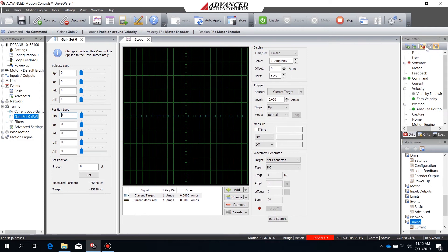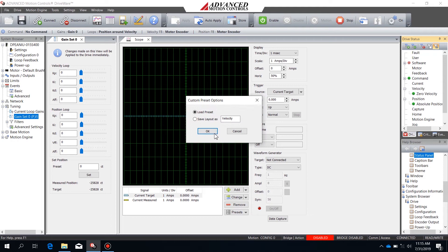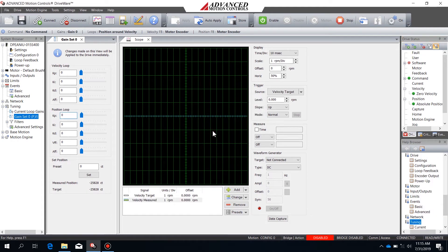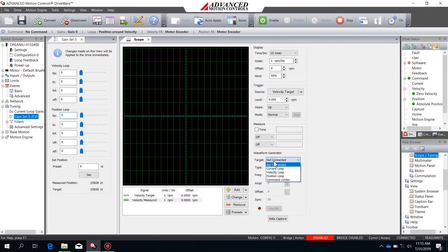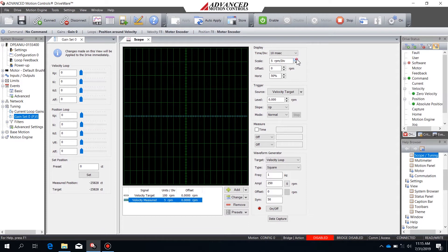Throughout the process I'll reset events from time to time in case I'm running into any issues with a faulting event. I'll change the presets to velocity so the basic presets are configured, then configure the waveform generator for velocity loop with the type set to square wave. I'll keep the frequency at one hertz and set the amplitude to a typical RPM I'll need to achieve quickly — in my case, 250 RPM. Then I'll adjust the scaling, leaving time per division at 10 milliseconds and scaling to 100 RPM per division so everything is visible on the screen.